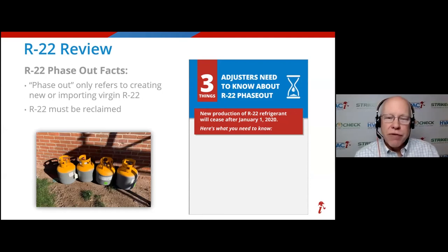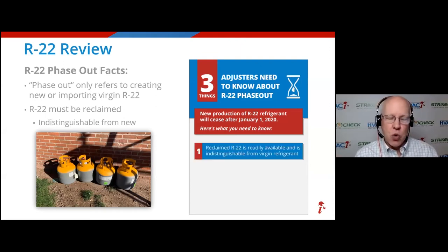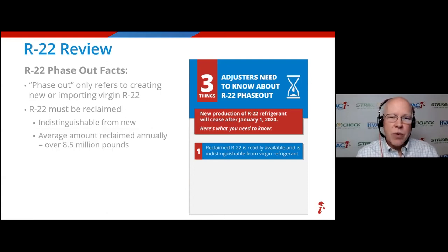So here's where the conversation continues that you're not hearing anywhere else. Per the Montreal Protocol for the last dozen years, it's been required that all R22 coming out of systems must be reclaimed. Okay, it goes to a reclamation center, they boil it down and bring it back to new. All right, reclaimed R22 is indistinguishable from brand new R22. You can't tell, I can't tell, the technician can't tell, and the system can't tell. All right, it's like new, and we've been reclaiming lots of R22. There was 40 million R22 systems still in existence, and they just come to the end of their lifespan. We take the R22 and we reclaim it.